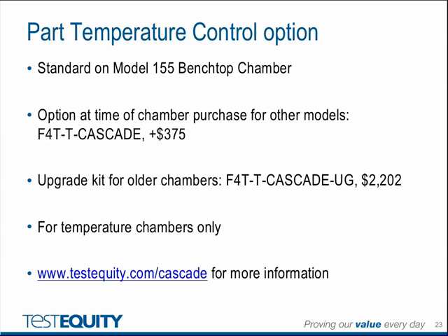We have a retrofit kit for older chambers. We have thousands of chambers in the field since 1998 that have the original F4 controller with arrow keys. They can be upgraded with an F4T touchscreen controller and Cascade Control for about $2,200. The controller can be easily installed by anyone who has moderate mechanical skills.